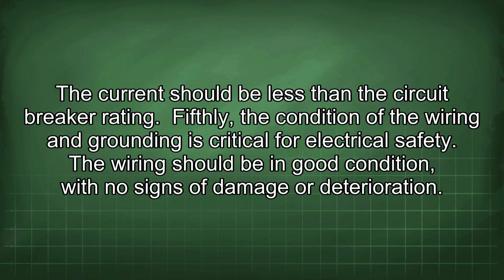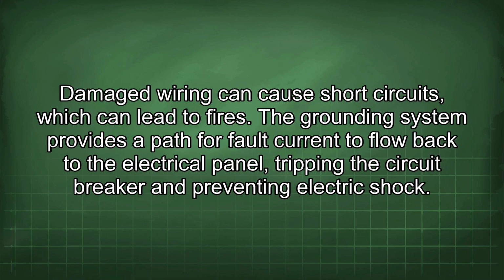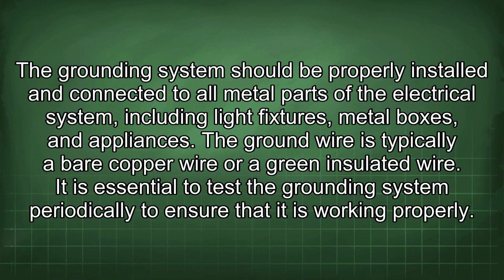Fifthly, the condition of the wiring and grounding is critical for electrical safety. The wiring should be in good condition, with no signs of damage or deterioration. Damaged wiring can cause short circuits, which can lead to fires. The grounding system provides a path for fault current to flow back to the electrical panel, tripping the circuit breaker and preventing electric shock. The grounding system should be properly installed and connected to all metal parts of the electrical system, including light fixtures, metal boxes, and appliances.